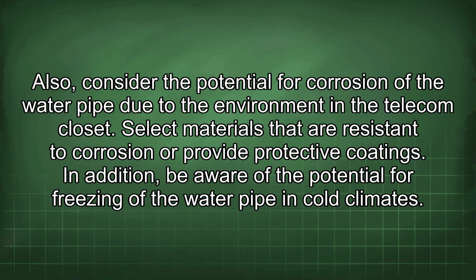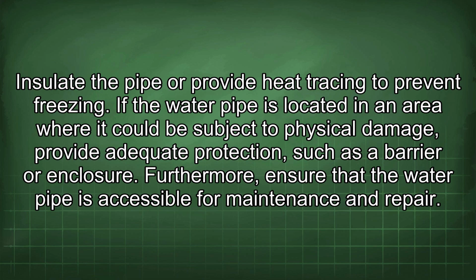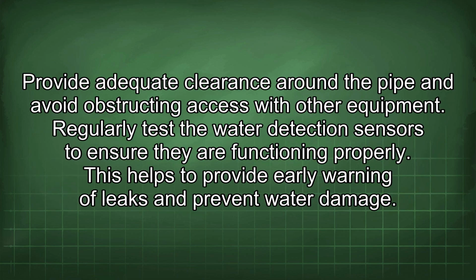In addition, be aware of the potential for freezing of the water pipe in cold climates. Insulate the pipe or provide heat tracing to prevent freezing. If the water pipe is located in an area where it could be subject to physical damage, provide adequate protection, such as a barrier or enclosure. Furthermore, ensure that the water pipe is accessible for maintenance and repair. Provide adequate clearance around the pipe and avoid obstructing access with other equipment.